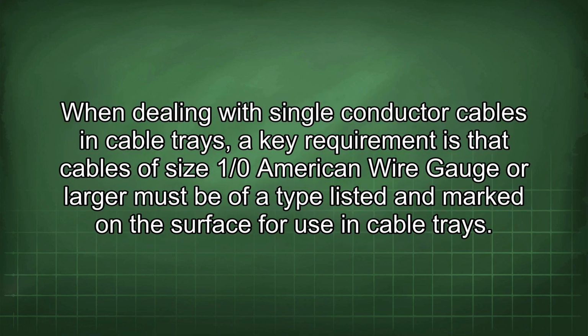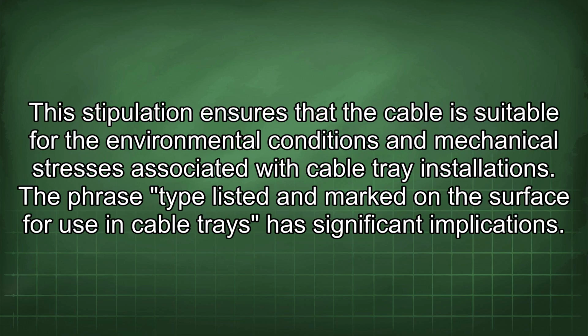When dealing with single conductor cables in cable trays, a key requirement is that cables of size 1/0 American wire gauge or larger must be of a type listed and marked on the surface for use in cable trays. This stipulation ensures that the cable is suitable for the environmental conditions and mechanical stresses associated with cable tray installations. The phrase "type listed and marked on the surface for use in cable trays" has significant implications.